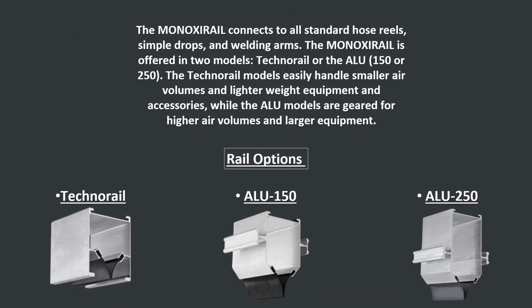Now, we have 3 different types. We have the Techno Rail, which is the most popular, and the trolley wheels ride on the inside of the rail, and basically we do that up to about 6-inch diameter. So if you think about it like sizing ductwork, anything up to about 6-inch, 600 CFM per drop, we would use the Techno Rail. Then when we get into larger applications, we would bump it up to the ALU 150, and even larger up to the ALU 250. And we can go larger than that, maybe for trains and things like that.